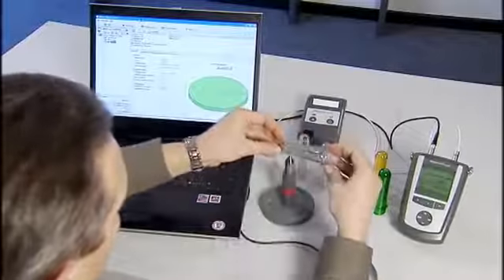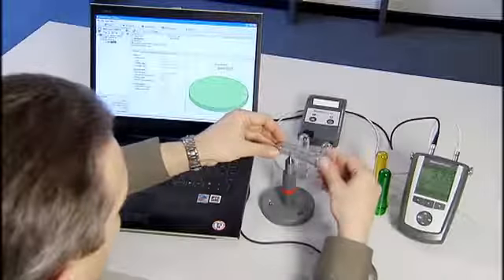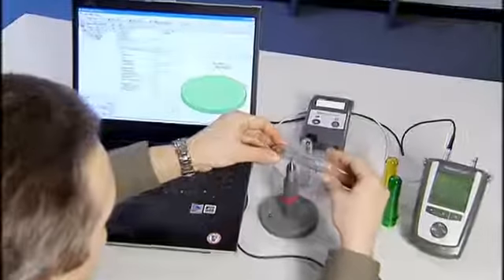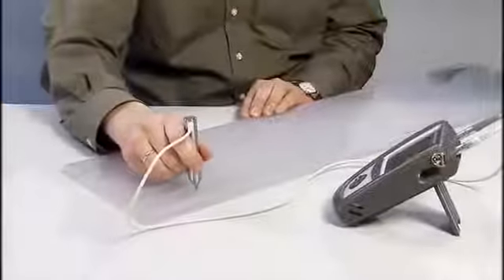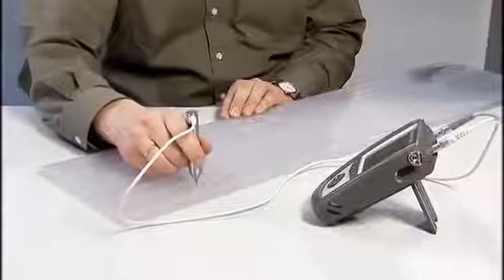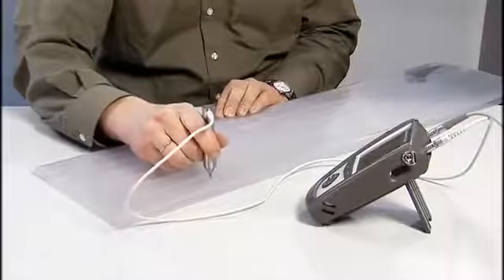Both models offer data output to external devices such as a computer, data collectors, analyzers or printer for further evaluation. To obtain accurate readings, the gauges must be calibrated for your measuring series. The gauges offer three different calibration modes.